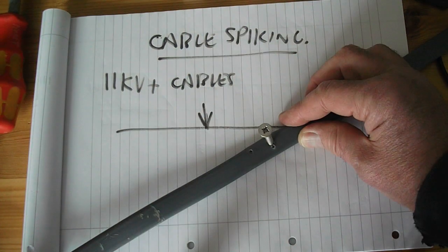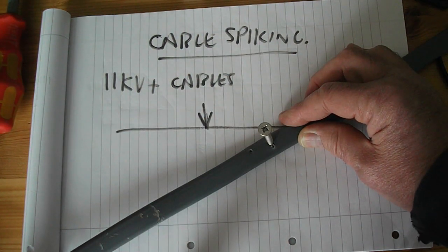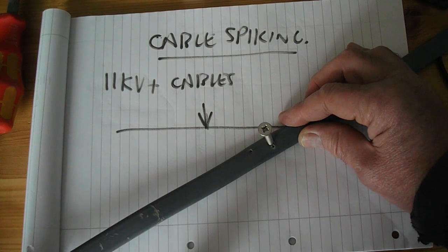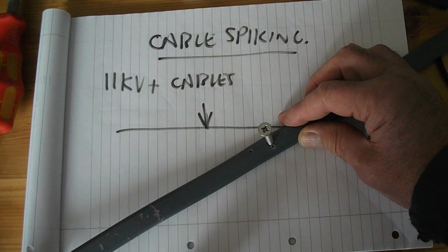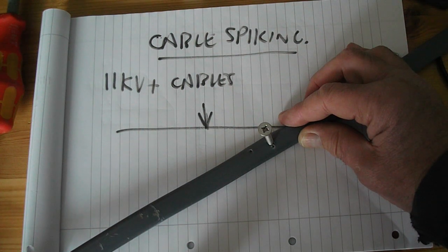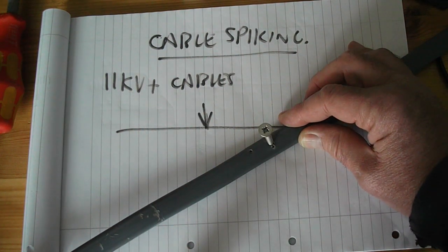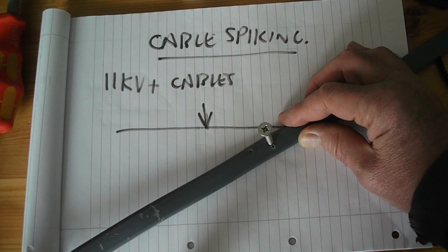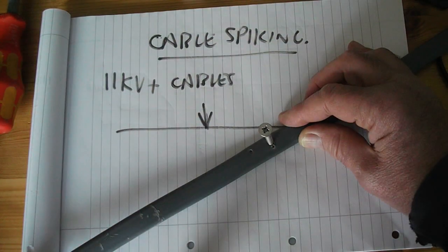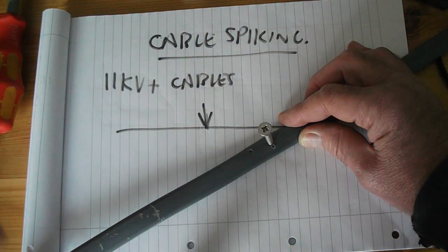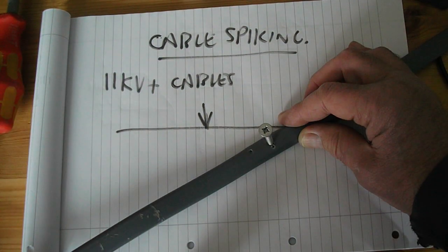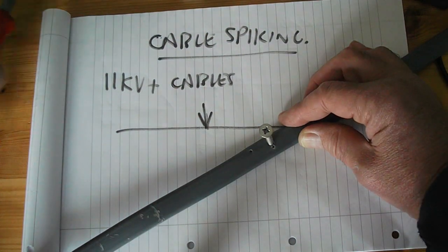Now the idea with cable spiking is that the cable is disconnected by usually a senior authorised person in your company, and they will then authorise you to spike the cable, because there's no real safe way of determining whether a cable is live or not from external testing. So the only way to prove it 100% is to fire a bullet into the cable and determine whether it's dead. So what you're proving is that it is actually dead, not live. In this situation, I've shown it's effectively live.